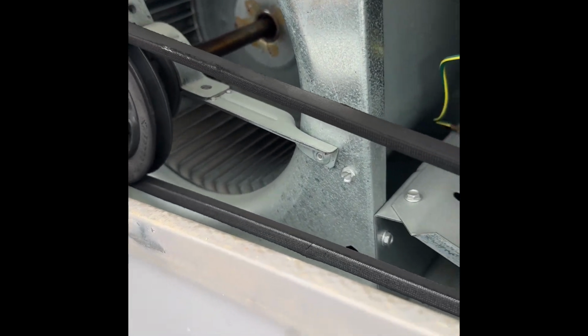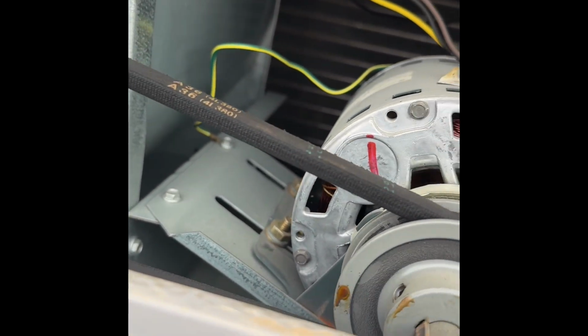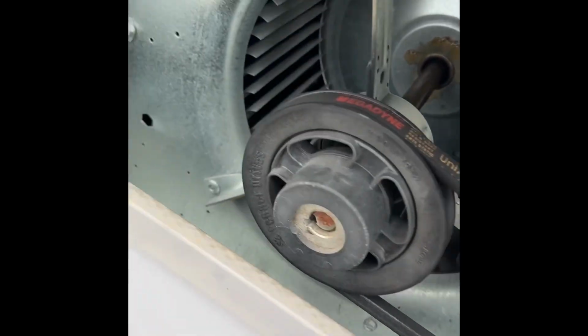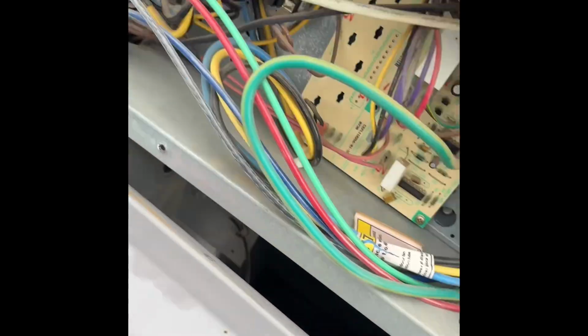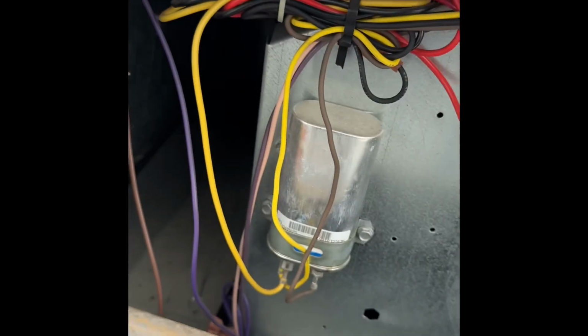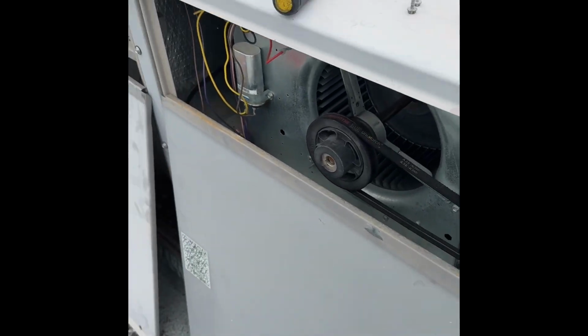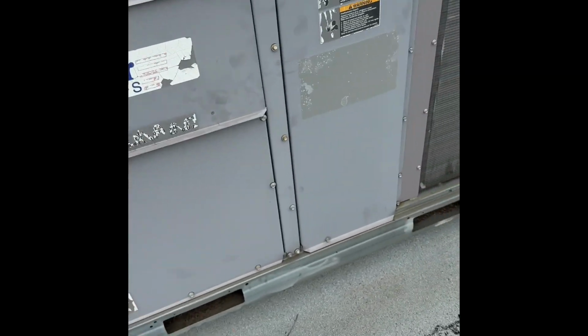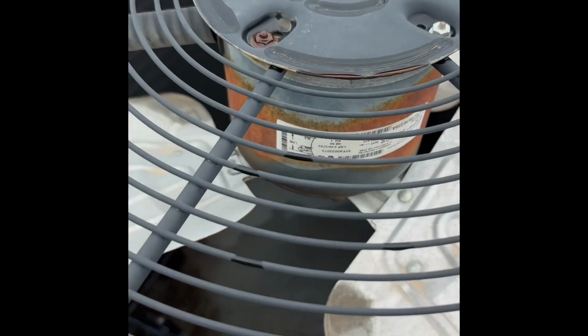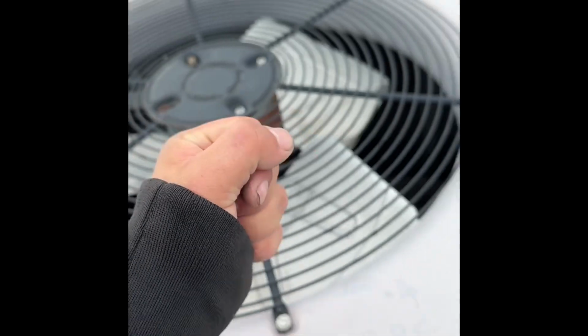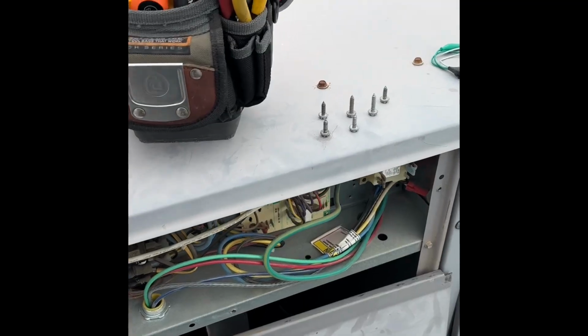So visual inspection for the PM. Obviously you want to check your blower motor, check the belt, make sure there's no rips or tears. Visual inspection first, right? And you're gonna check capacitors. I already took care of that as well. And I have a video, I believe, showing how to check and run capacitors, so check my channel for that. So visual inspection, check the coil. I already changed the filters. Check the compressor if need be. Visual inspection on the outdoor fan motor. Test it, check the shaft bearing for shaft play, or if it's not spinning good enough, might be time for a replacement soon before next summer.